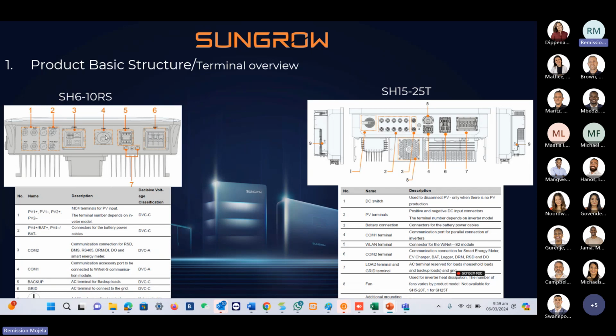And then for the communication module, we use the WiNet-S on the 6RS, the WiNet-S2 on the 10, and the WiNet-S2 on the 15 and the 25. It's also in the box. You don't have to buy it, by the way. All the devices that you need to do the installation are in the box, like I said in the beginning. And then I'm just going to highlight the points where you're going to connect.